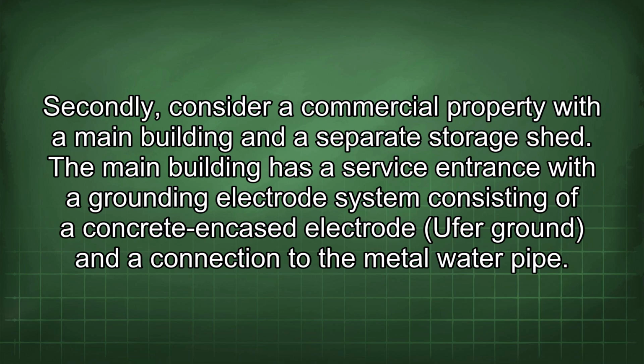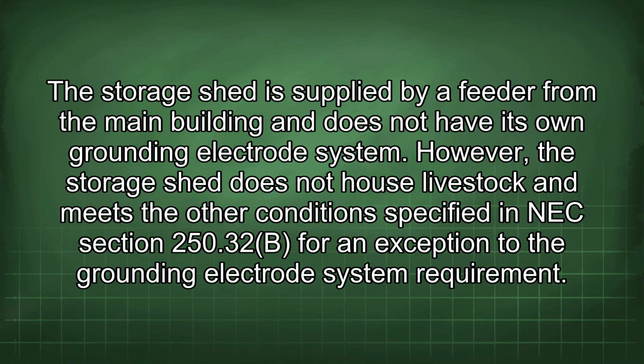Secondly, consider a commercial property with a main building and a separate storage shed. The main building has a service entrance with a grounding electrode system consisting of a concrete encased electrode, a Ufer ground, and a connection to the metal water pipe. The storage shed is supplied by a feeder from the main building and does not have its own grounding electrode system. However, the storage shed does not house livestock and meets the other conditions specified in NEC Section 250.32(B) for an exception to the grounding electrode system requirement.